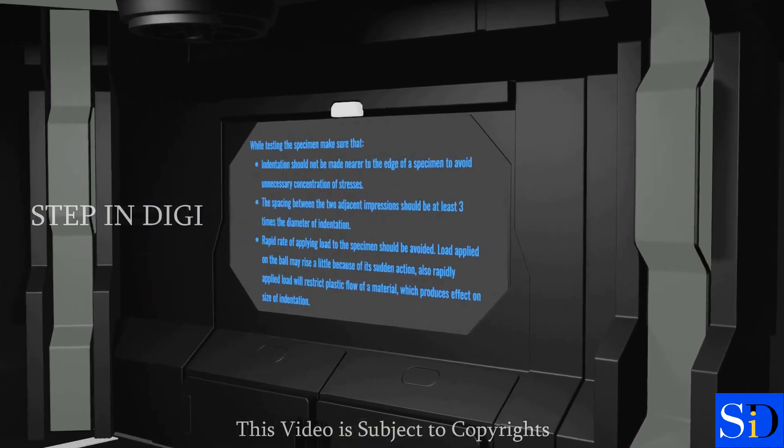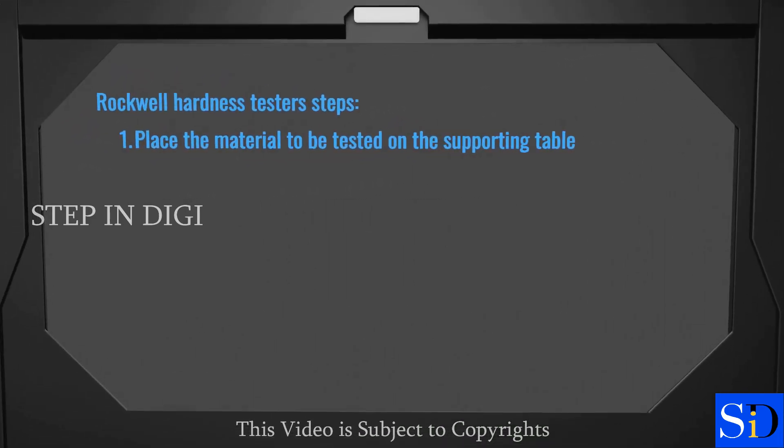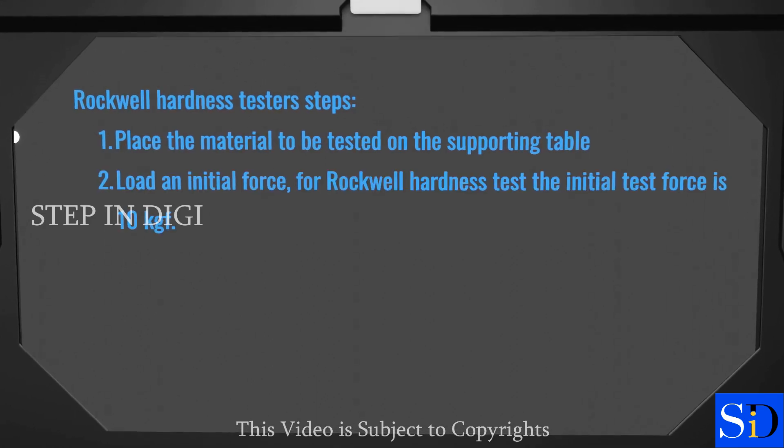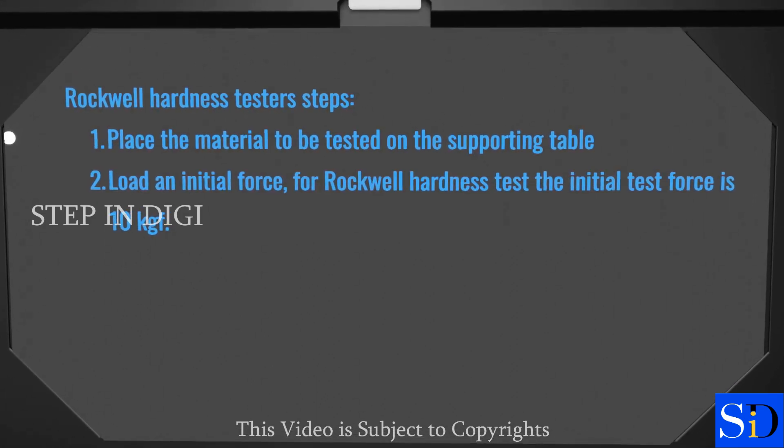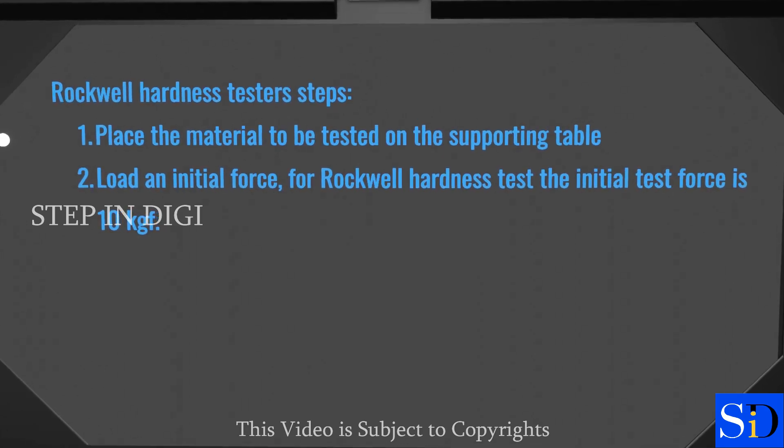Rockwell hardness test has the following steps in common for all materials. Step 1: Place the material to be tested on the supporting table. Step 2: Load an initial force. For Rockwell hardness test the initial force is 10 kgf.